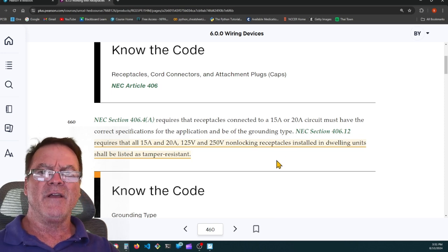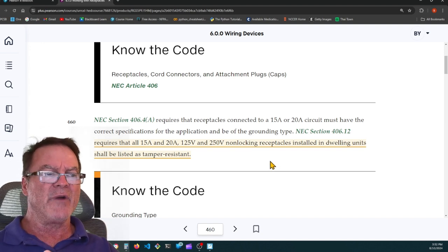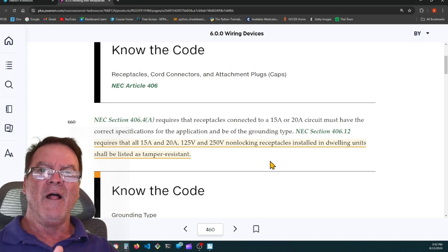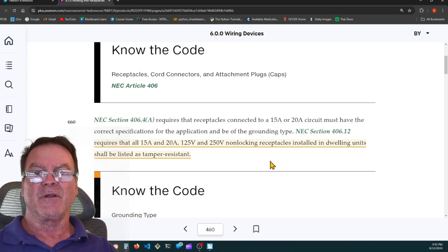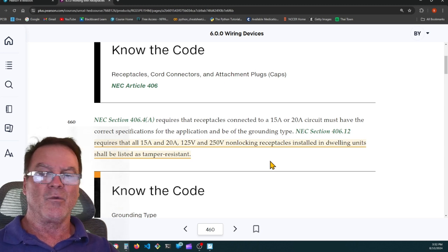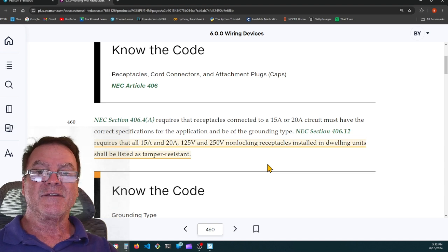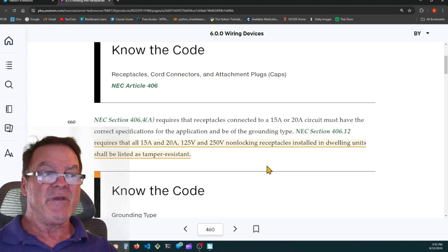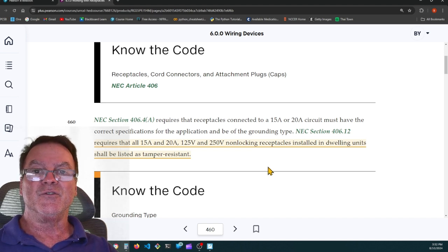And on a circuit, if you have a single receptacle on a dedicated circuit, the receptacle has to have a rating equal to or greater than the rating of the circuit. In other words, if you have a 50 amp single receptacle for a range, it has to be on a circuit that is rated no more than 50 amps. It can be on a circuit that's rated 40 amps. The receptacle rating has to be equal to or greater than the individual circuit.